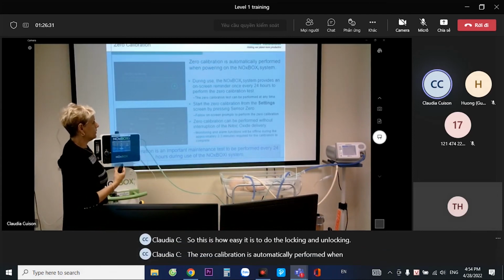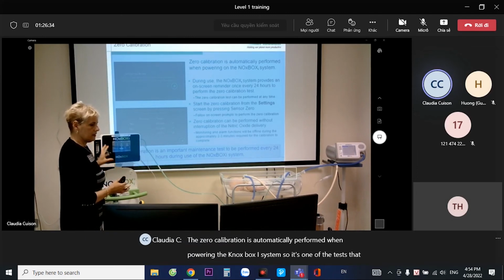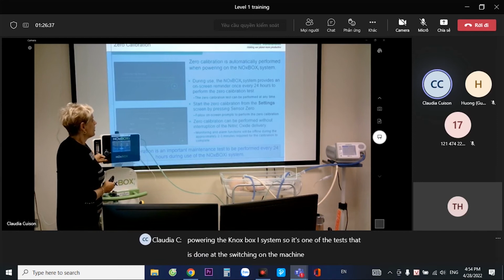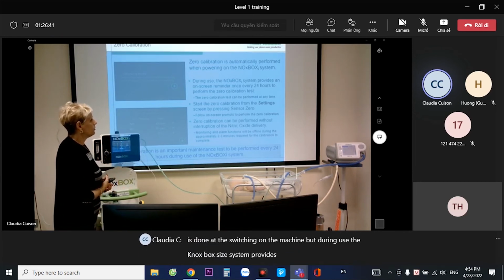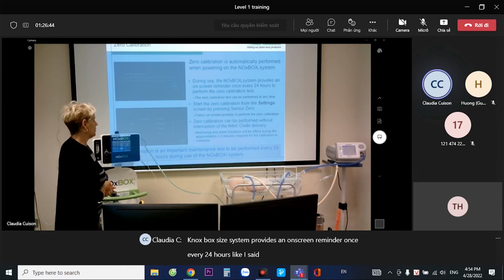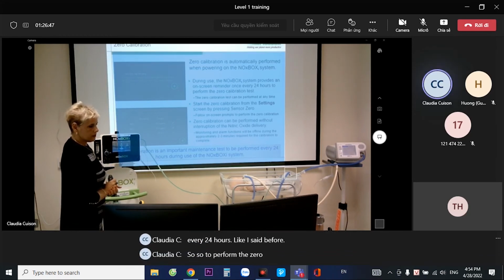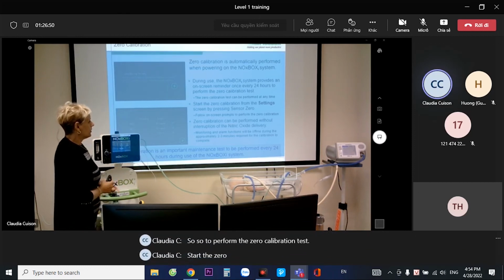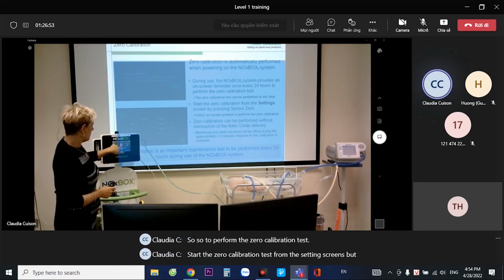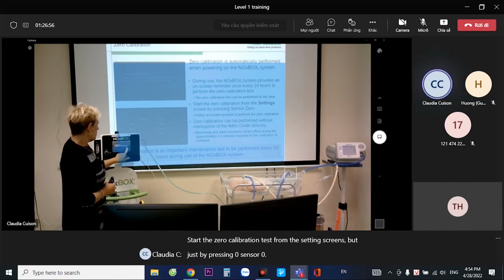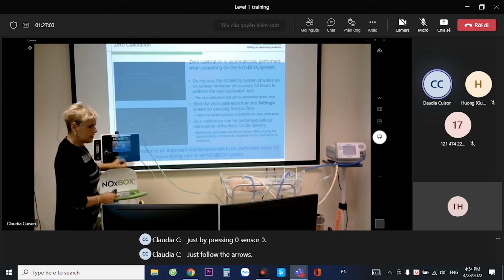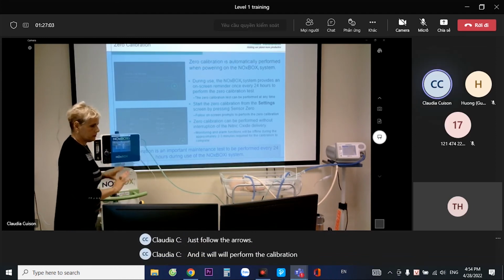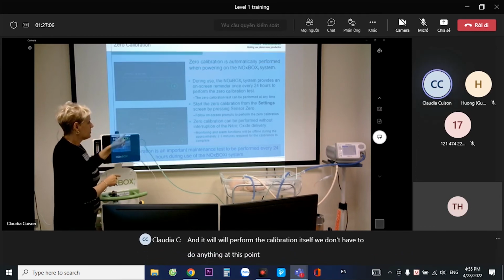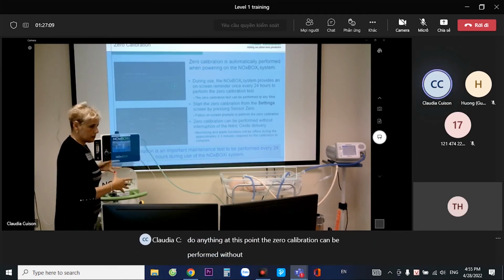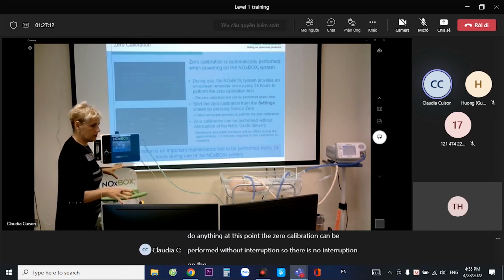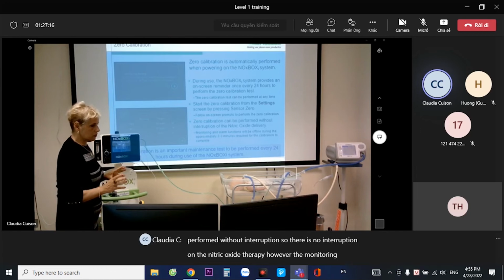The 0 calibration is automatically performed when powering the NOxBOX system. So it's one of the tests that is done at the switching on of the machine. But during use, the NOxBOX system provides an on-screen reminder once every 24 hours, like I said before, to perform the 0 calibration test. Start the 0 calibration test from the setting screens just by pressing 0, sensor 0. Just follow the arrows, and it will perform the calibration itself. We don't have to do anything. At this point, the 0 calibration can be performed without interruption, so there is no interruption on the nitric oxide therapy.